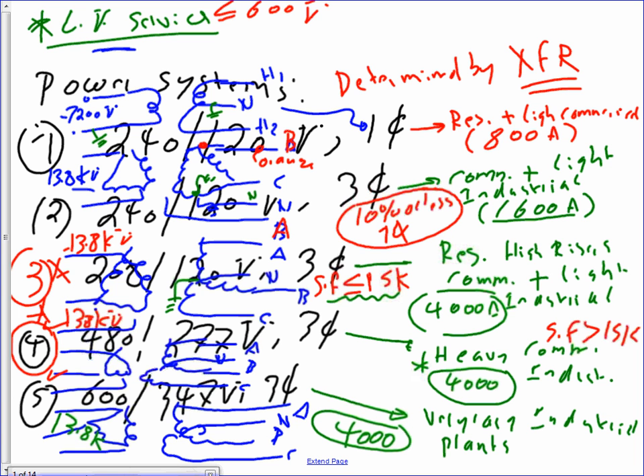Okay, the second system that we use, so that's my system. The second 3-phase system that we use, guys, in the US, these are the most common systems in a commercial industrial building. System number 3: they give you 13,800 volt on the primary. On the secondary side, they give you 208/120. That's the system that we're using. It's a 3-phase system. Typically, if the building is a commercial building, square footage of 15,000 or less, we recommend this system, like the building that we have, guys, and it's used for residential high-rises, commercial, light industrial, up to 4,000 amp.